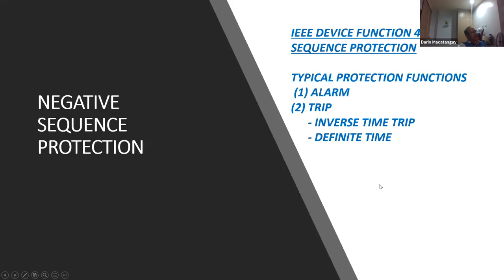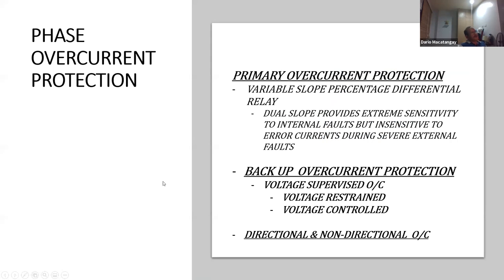All right, so for negative sequence current, you need to use device function 46, which again has alarm and trip. So you set that inverse time and definite time. That will be dependent on the study that you have to do in order to set this. Okay, so it depends on the allowable negative sequence unbalance that the generator can handle. So you have to set it from there. Okay. Now, phase overcurrent. The typical protection that's used there is differential protection and overcurrent protection.